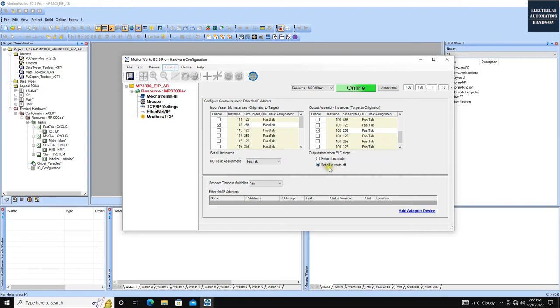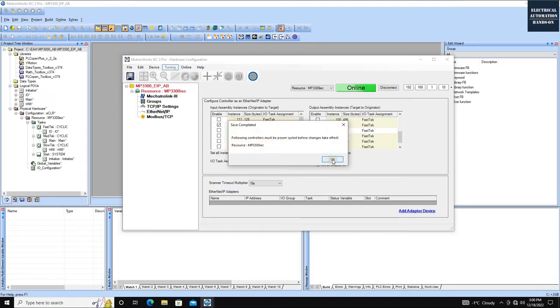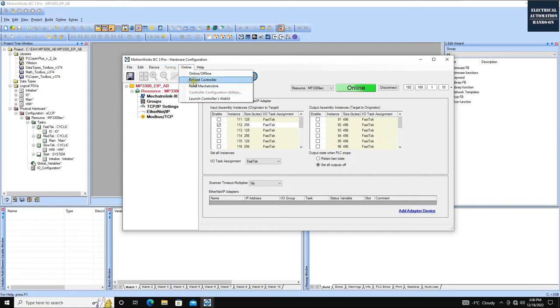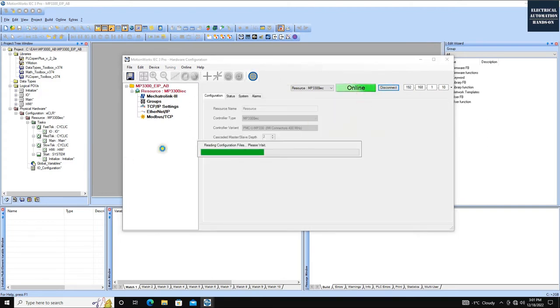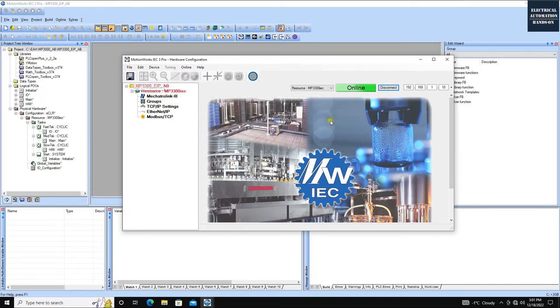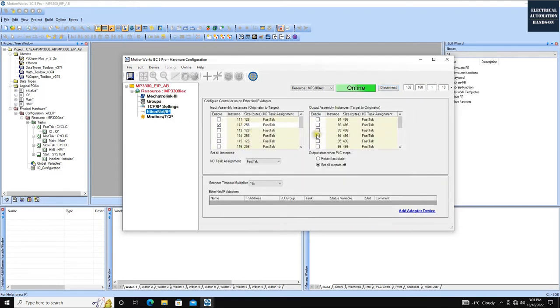I recommend setting all outputs to OFF when communication is lost, as retaining commands like a jog could be dangerous. Now we've finished all settings. Click Save and then Cycle Power. The configuration is transferred to the controller — reboot. After rebooting, click Connect. The system doesn't show any difference, meaning we saved the configuration successfully and the controller is loaded with this configuration.